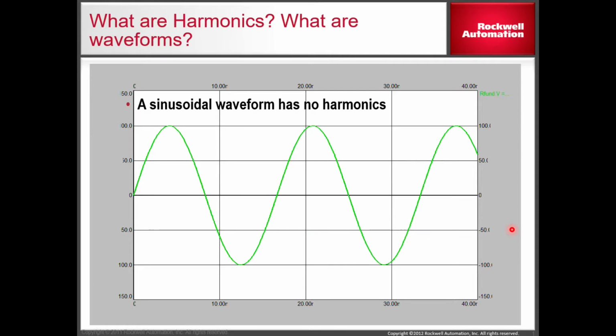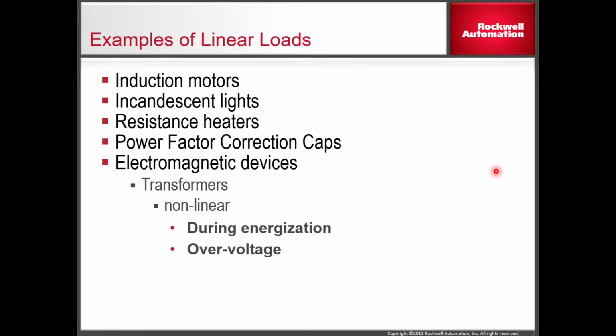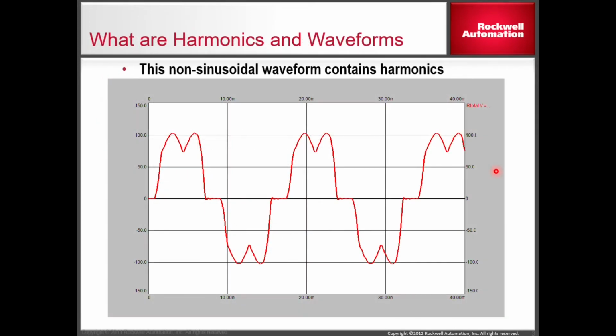So we put a scope on our power system, and this is what we see. This is great. That's exactly what we want to see. But that would be a plant with just linear loads in it. And what are linear loads? Induction motors, incandescent lights, resistive heaters, etc. But we've introduced drives and other switch mode power supplies into our plant, and if they get to be too great, the harmonics generated will make our sine wave look like this. Not so pretty, huh?